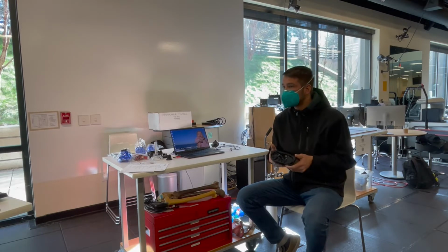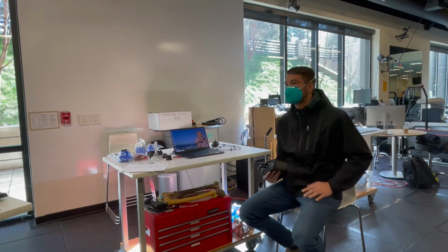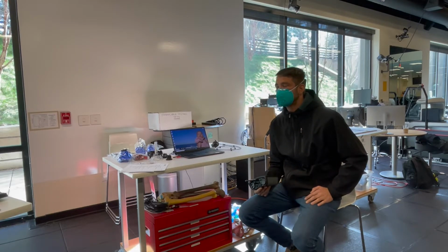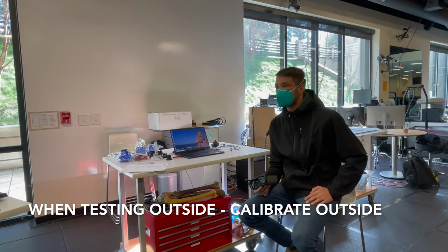It said it's 0.09, you tested it? Yes. Okay. So if we're doing a test outside, we have to calibrate outside. You want to calibrate outside. So don't calibrate it here and then take the device outside. Yeah, got it, or vice versa.